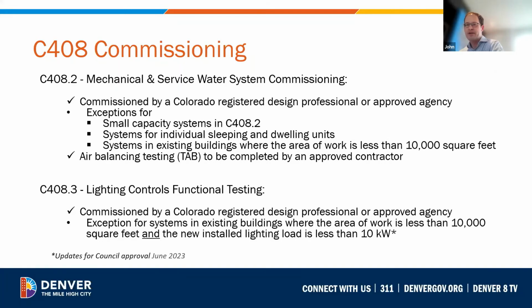Under section C408.3, lighting systems must be commissioned when the new installed lighting load is 20 kilowatts or greater and the work area is 10,000 square feet or more. There are plans in the future to possibly update this threshold from 20 kilowatts to 10 kilowatts. Again, this is flagged for an approved update in June that should be pending. Please check with Denver for that update. Existing buildings undergoing a major equipment replacement of the same capacity thresholds will require commissioning when most of the devices directly connected to that equipment are also being replaced, such as in a complete floor demolition.